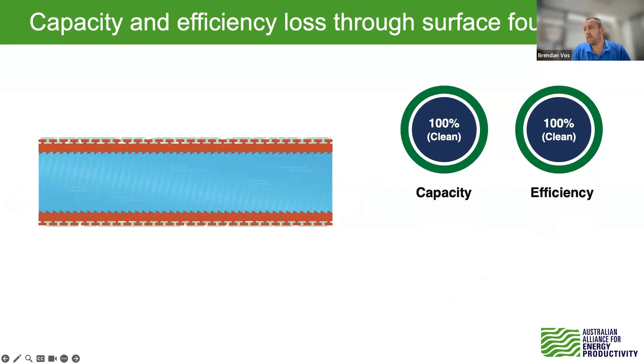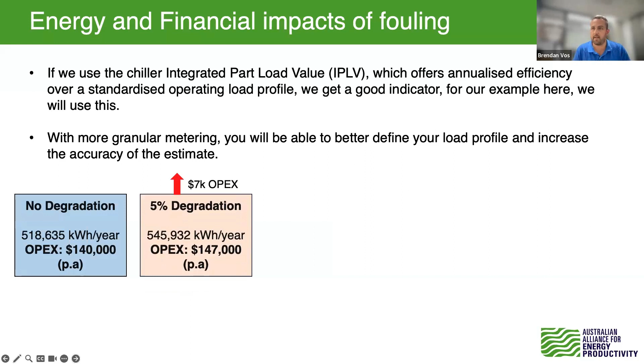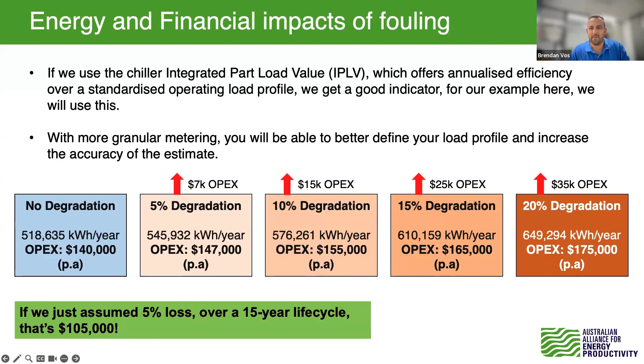Now, how you monetize that in terms of the maintenance, I mean, the maintenance is often not very expensive. That sort of tube cleaning exercise is often less than 1 day of time for a chiller technician to do. So let's assume that this plant is performing at $140,000 a year. If I lose 5%, I'm at $147,000. So there's my $7,000. That 1 day of labor now seems very cheap because I'm just going to keep that happening. And so on and so forth, all the way down to the point where you can be 35,000 plus very, very easily if you're running that plant quite regularly. So the point here is if we just assumed we hit 5% loss and that no one ever picked that up and we never fixed it from year 1, we would lose $105,000 in 15 years. That is quite substantial, and makes my maintenance costs seem now very cheap.